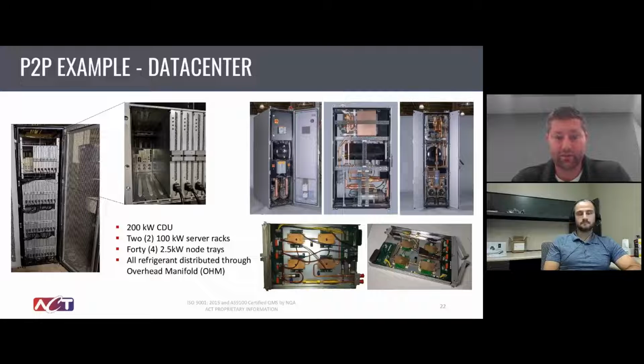And this one, instead of being air cooled, had a liquid to liquid heat exchanger up top. So it was using facility water as the ultimate coolant there, with a liquid heat exchanger to exchange heat between the dielectric refrigerant and the facility water. From there, the CDU provided the fluid to the data center blades itself. You can see the rack to the far left, and then the individual blades at the bottom of the screen there.